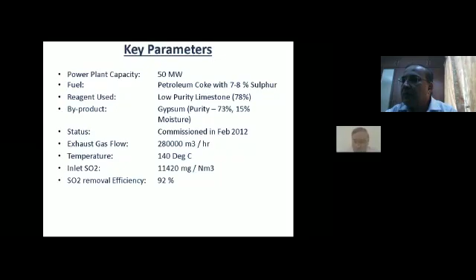Limestone consumption is almost 4.3 tons per hour. Water consumption is 18 meter cube per hour. And the gypsum generated is almost nearly 1.5 times the quantum of limestone. We are using 4,300, and on that basis it is almost 7,500. You are getting gypsum almost 1.5 to 1.7 times, and that is the waste getting out. So this is a big challenge. Getting limestone is one challenge, and handling the gypsum which is produced as a byproduct is another challenge.